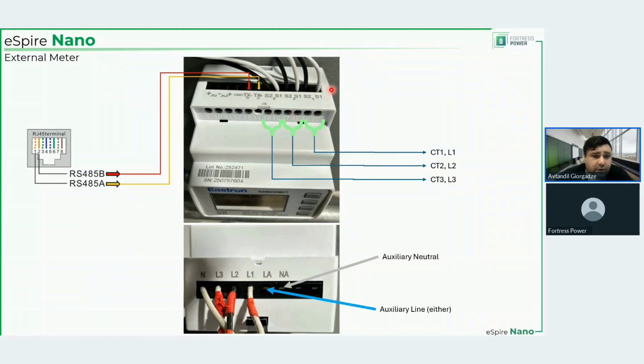You will also have CTs connecting right here, S1, S2, 3 pairs of such, so L1, L2, and L3. You have neutral, L3, L2, and L1 as your reference, connecting to the bottom of the meter, and auxiliary neutral connects here, and auxiliary line connects here. The way I am describing in the manual is, rather than having 3 cables coming in here and then an additional run of 2 wires connecting to LA and NA, what you can do is bring line 1 or line 2 or line 3, then use a Wago or something similar to split it.